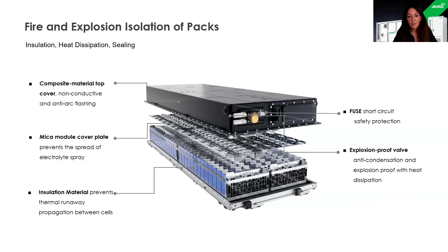For the packs, we have layers for insulation, heat dissipation, and sealing throughout. We have composite material on top as a cover, non-conductive and anti-arc flashing. Going from top to bottom: a mica module cover plate that prevents the spread of electrolyte spray, then insulation material that prevents thermal runaway propagation between cells, then a fuse for short circuit protection, and an explosion-proof valve as I mentioned. This is a quick overview.